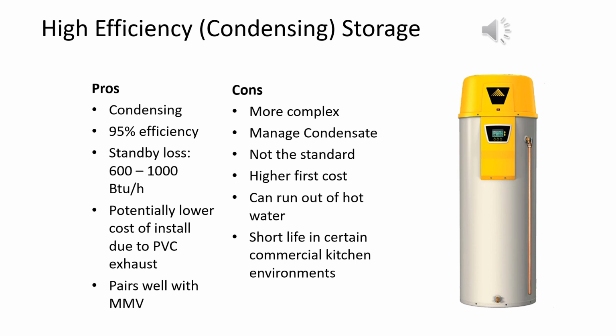The cons are that these are more complex, which means that they're harder to work on. When installing these water heaters, you have to manage the condensate. The condensate produced by these water heaters is usually fairly acidic, and so there needs to be some kind of buffer installed on the condensate drain or a condensate drain installed in the floor to handle that. These are not the standard, and so fewer plumbers can work on these. They have a higher first cost, so when they run out of water, they cost more to replace. And like other water heaters, they have a relatively short lifespan in certain commercial kitchen environments, especially ones where they run out of water often.